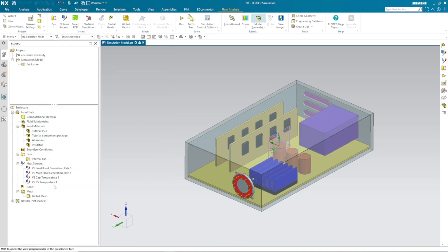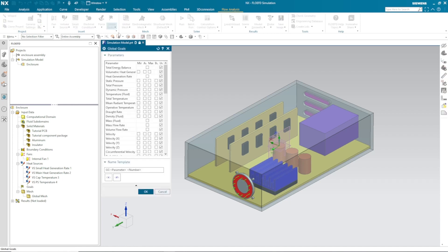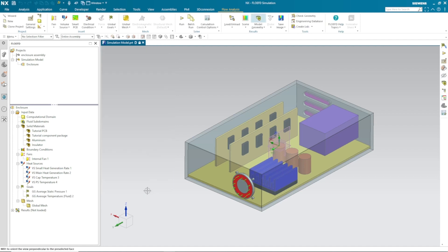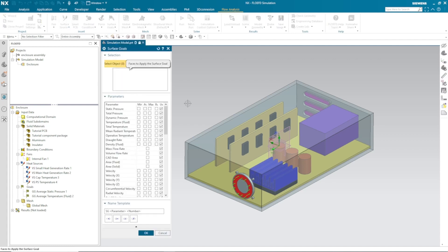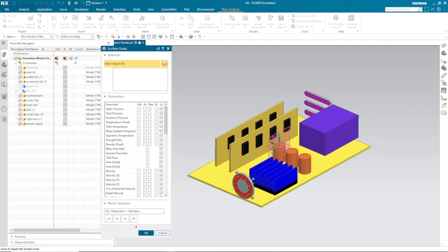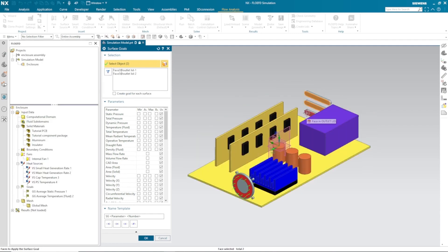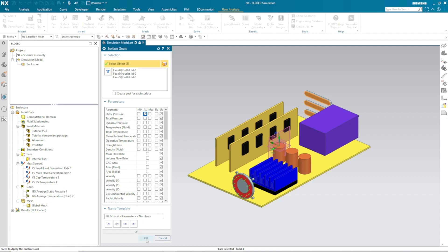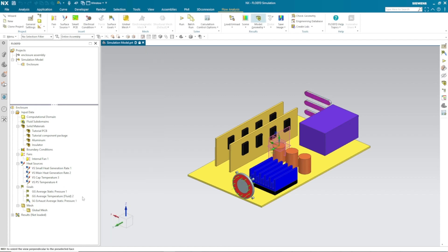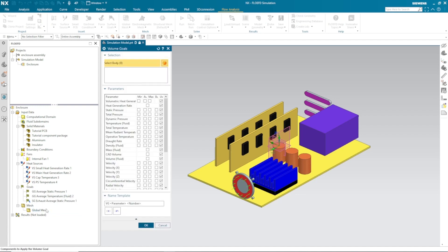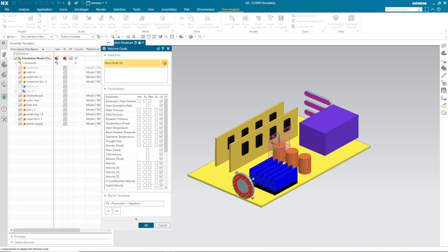Once our heat source is defined, next important thing is defining the goals which are considered for simulation convergence and to check some details. I consider global goal plot for static pressure and fluid temperature. Next thing is that I need to check the flow parameter on exhaust of this enclosure, so I have selected three magenta surfaces and need to check the static pressure at that particular location.